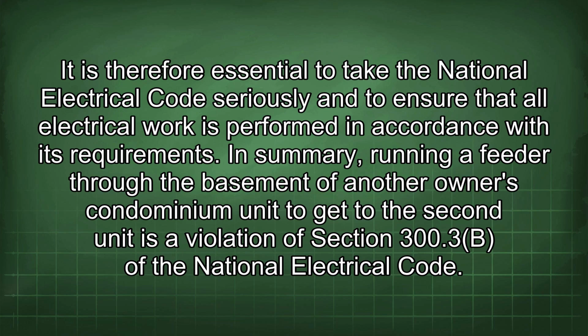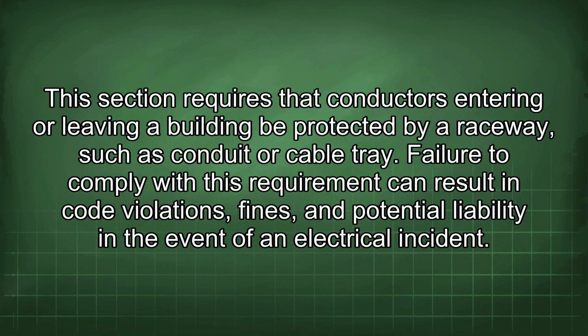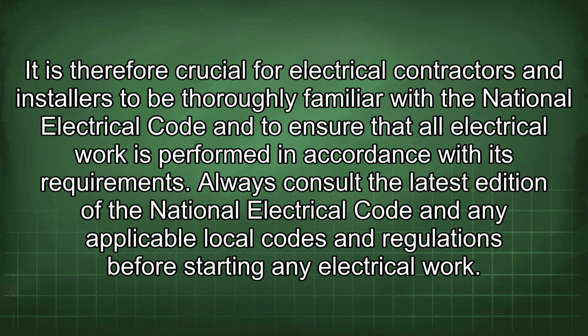In summary, running a feeder through the basement of another owner's condominium unit to get to the second unit is a violation of Section 300.3b of the National Electrical Code. This section requires that conductors entering or leaving a building be protected by a raceway, such as conduit or cable tray. Failure to comply with this requirement can result in code violations, fines, and potential liability in the event of an electrical incident. It is therefore crucial for electrical contractors and installers to be thoroughly familiar with the National Electrical Code and to ensure that all electrical work is performed in accordance with its requirements.